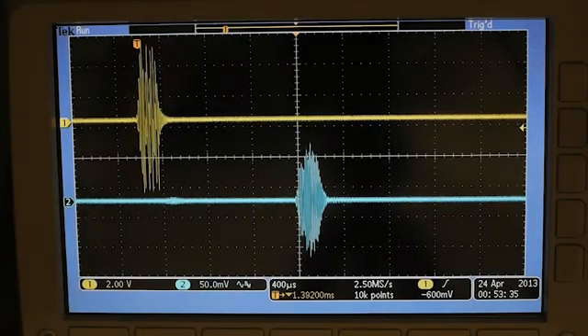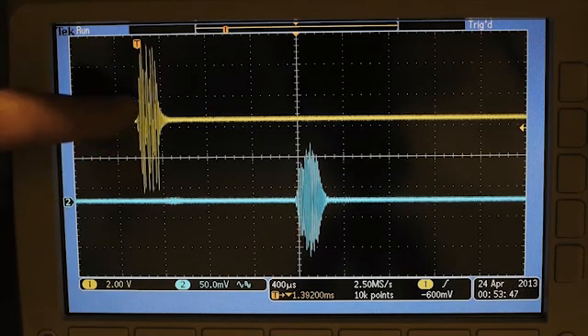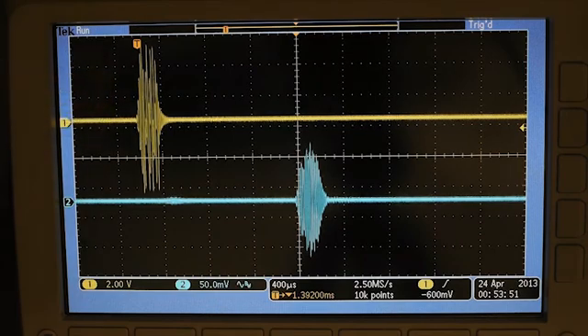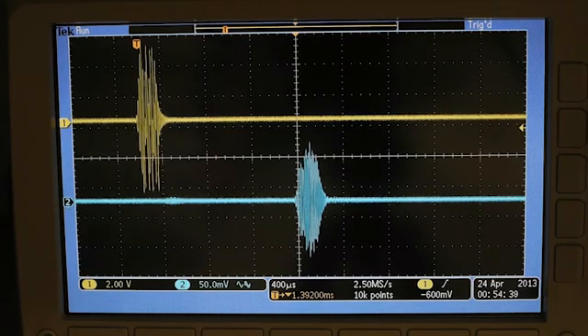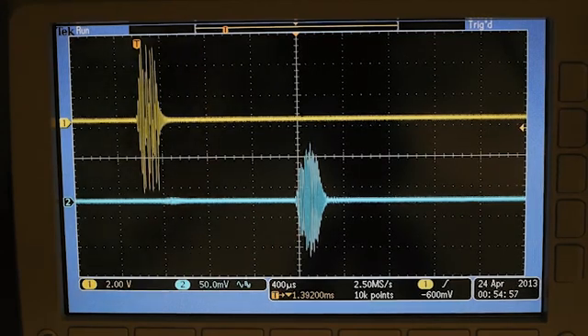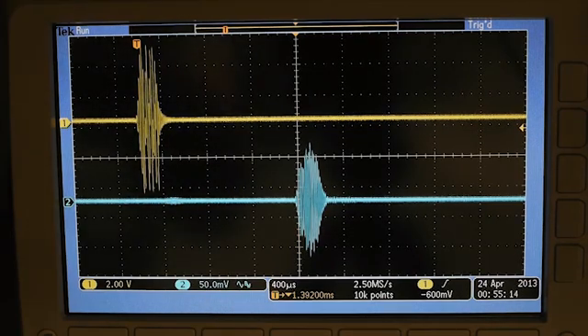We'll use the oscilloscope to look at the signal that we're using to drive our transmitter and our signal from our receiver. So the top trace here, channel 1, is the signal that we're using to drive our transmitter. The reason we're using a chirp with an FFT to analyze the data rather than a swept sine is to make sure that we avoid measuring the results of any standing waves in the tank or reflections. The reflections can be not just from the sides of the tank, which even though they have an anechoic lining, there can still be some reflection, but also from the water surface, or in this case, because we have two large transducers, large diameter, the sound can be reflected between them.